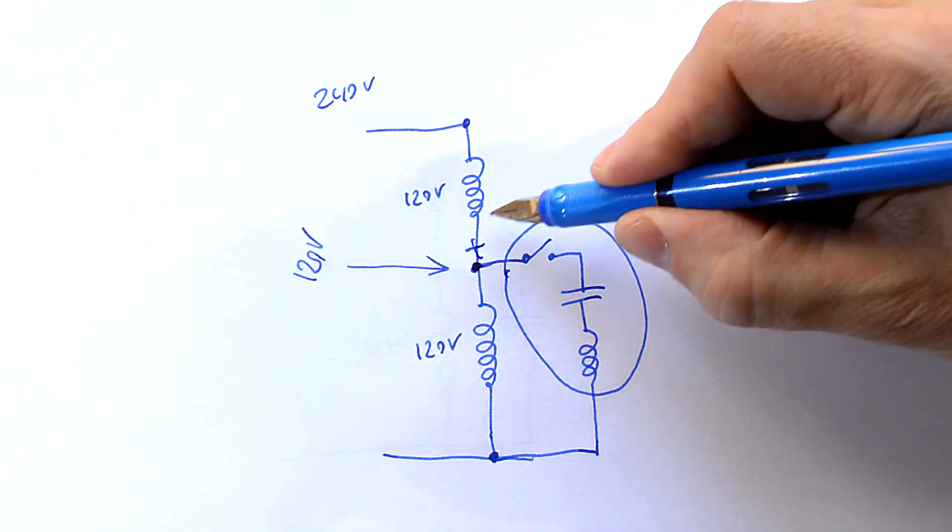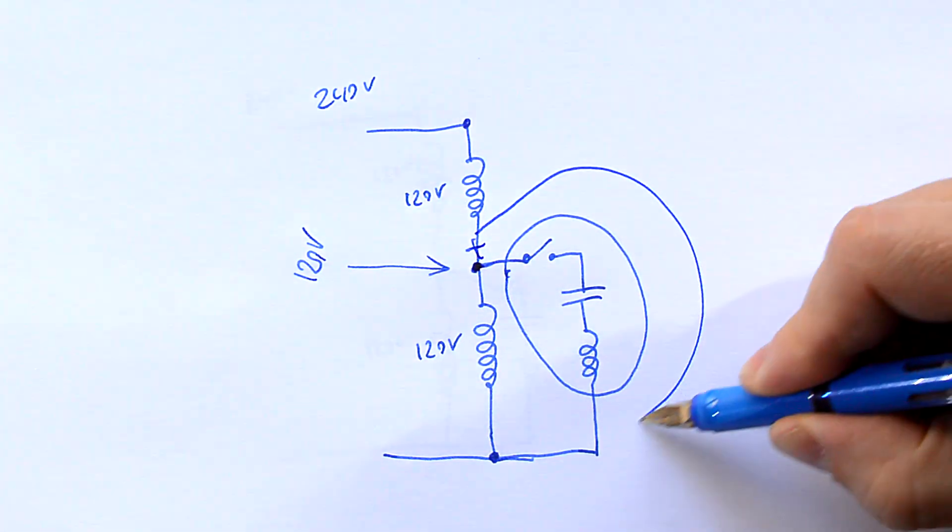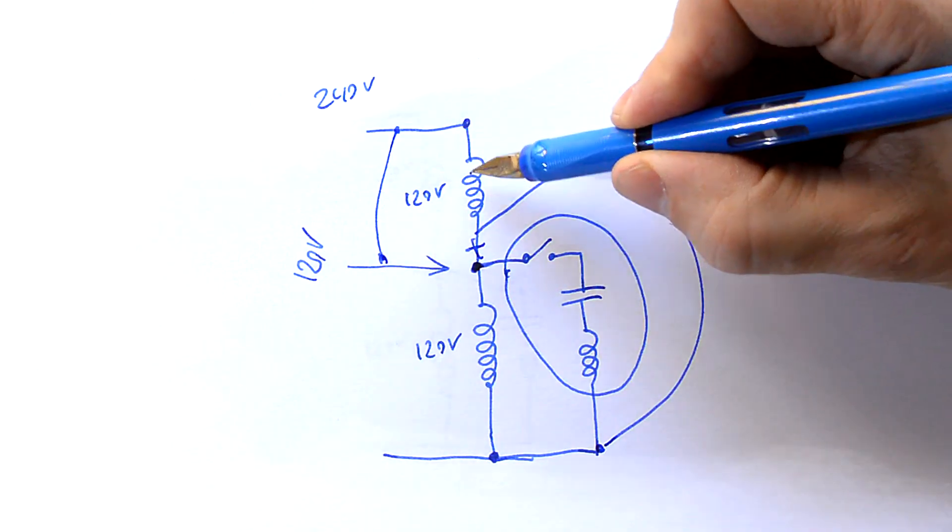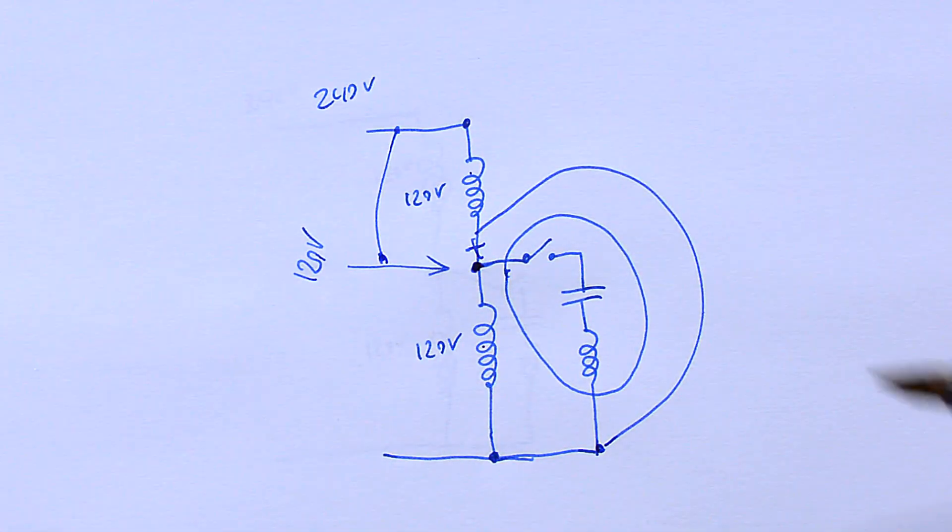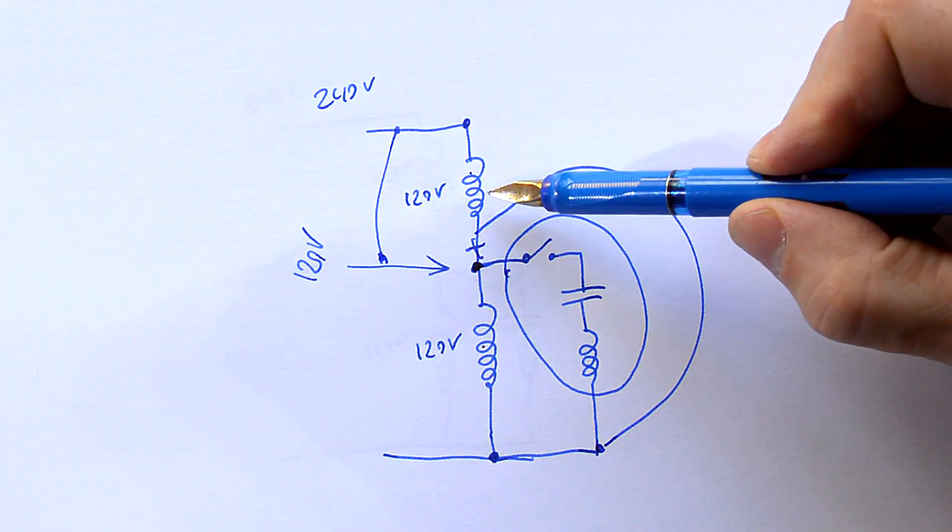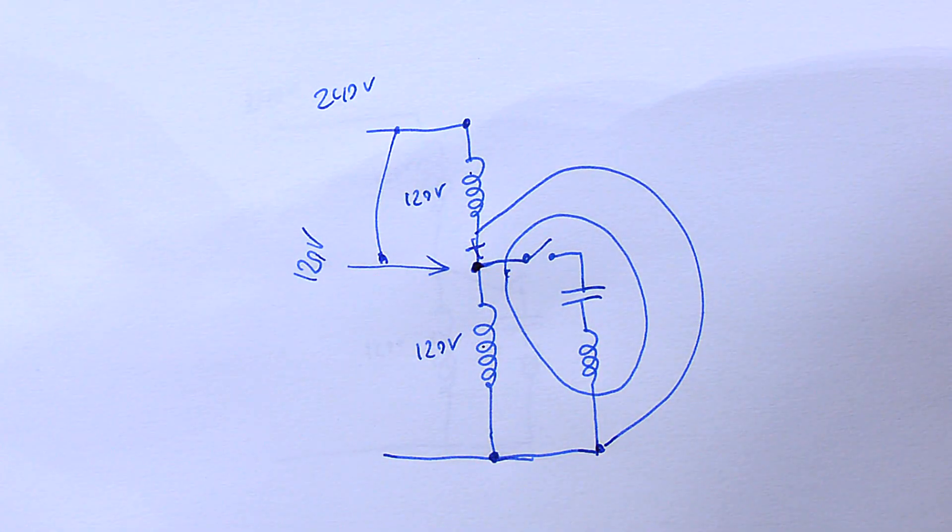And then we need to open this up here and connect that down here and this connects to here which puts these two windings in parallel. What's very important is we must not reverse this winding because if we do we're gonna blow the breaker very quickly.